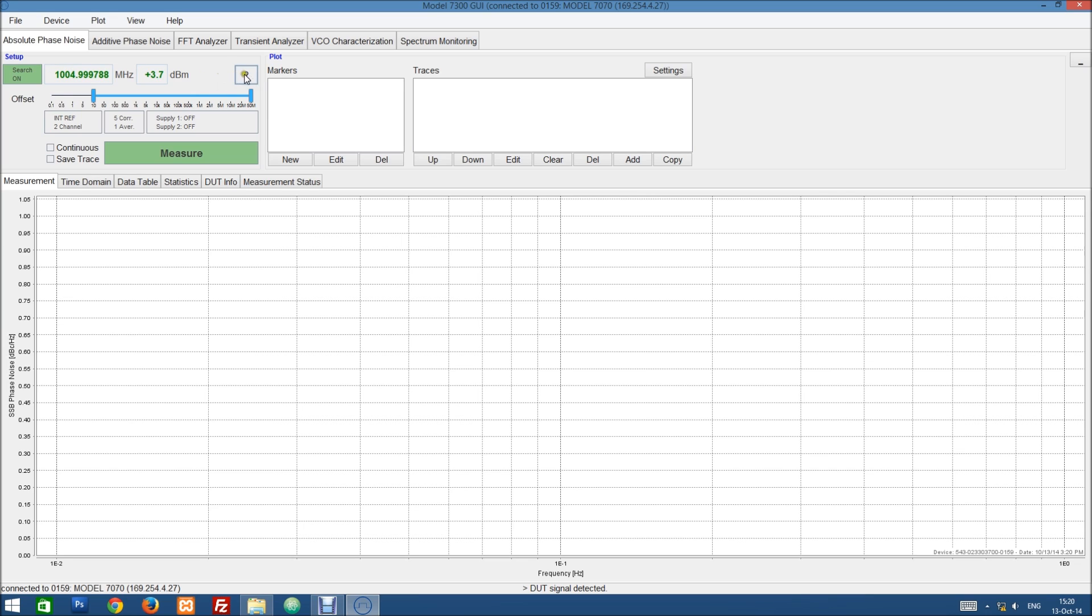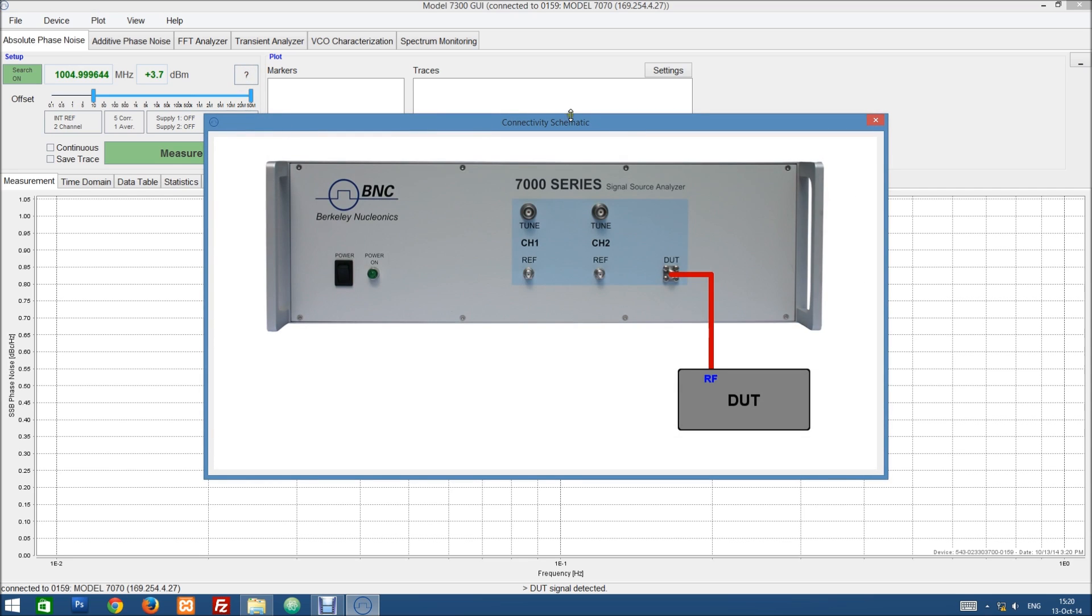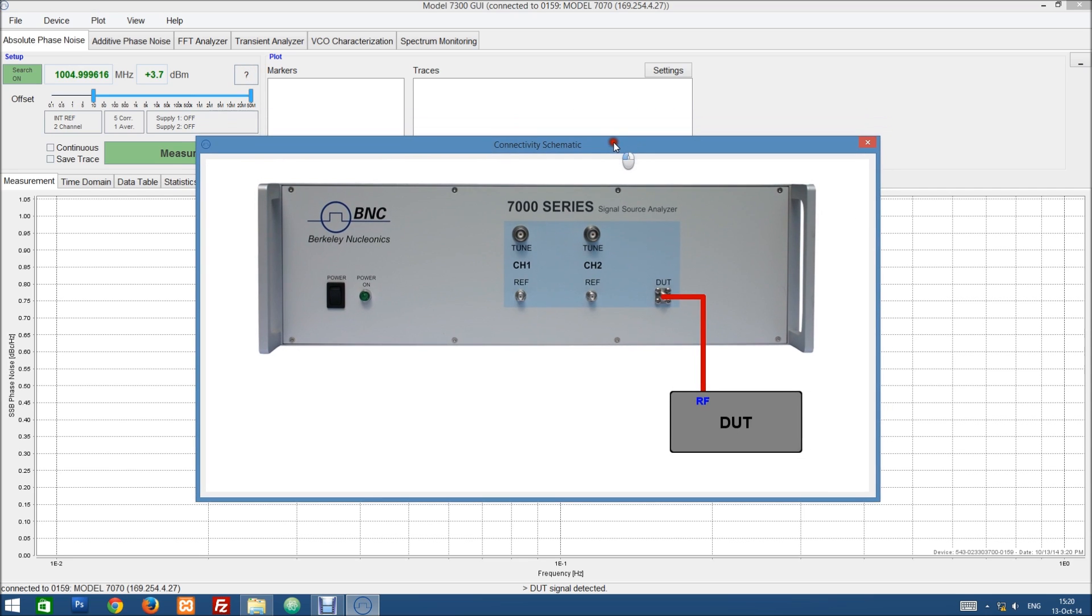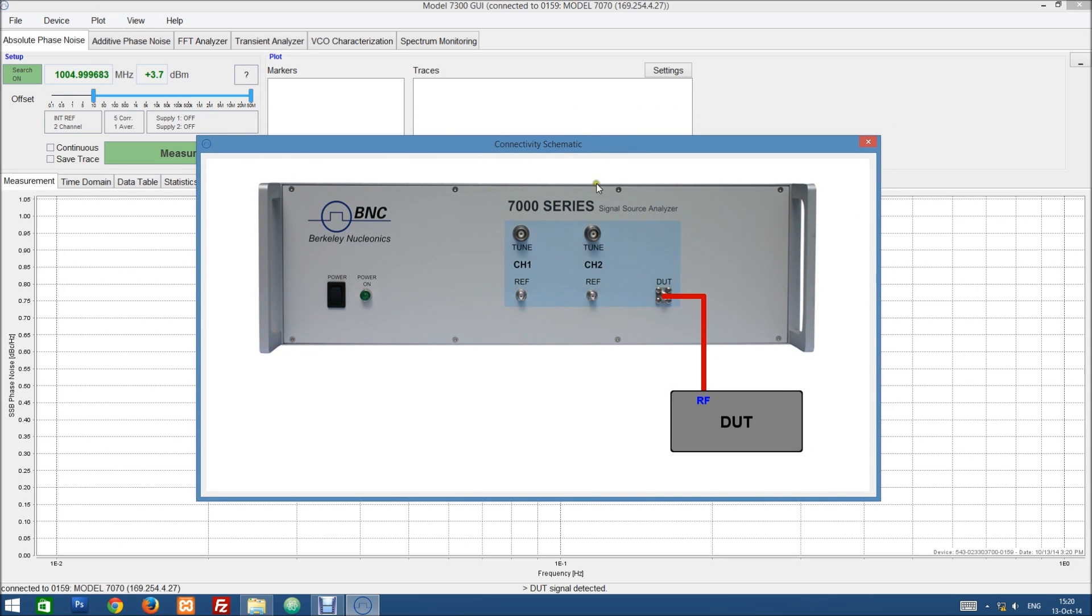Then we can first click on this question mark button. This will give us a connectivity schematic. In our case this is a pretty simple setup. We just have the DUT and we connect it directly to the DUT port of our signal source analyzer.